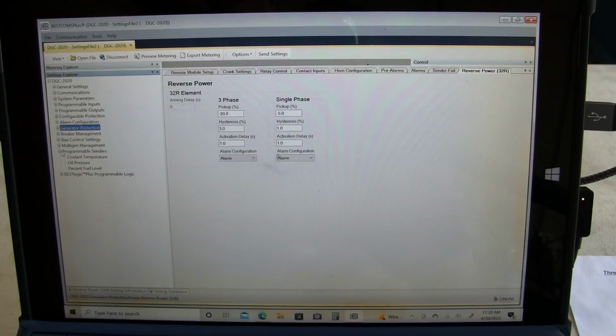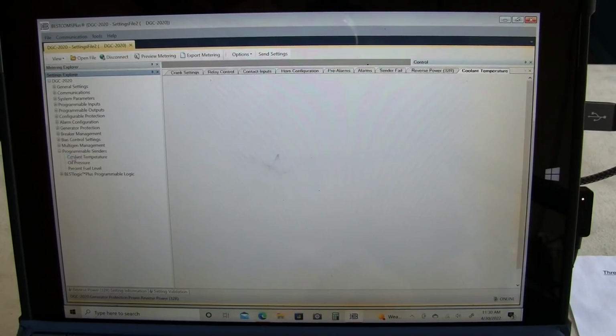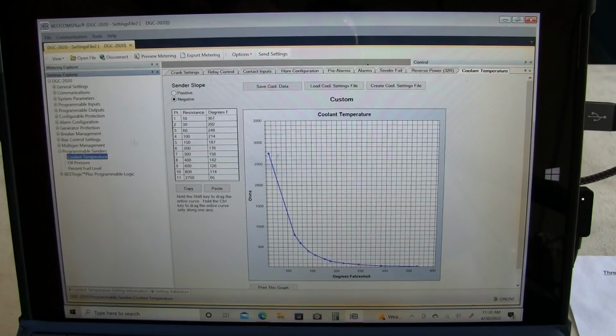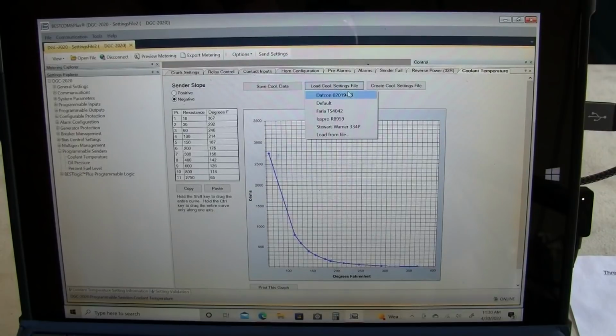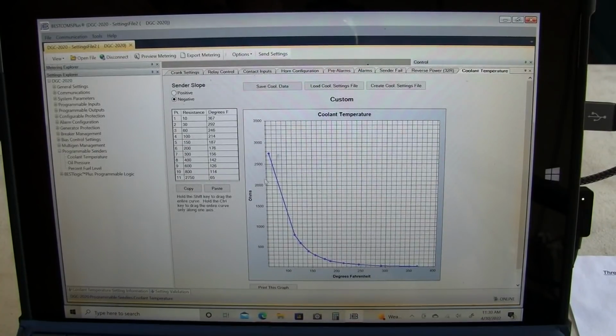Programmable senders. So there are multiple coolant temperature sensors available for these gensets, as well as oil pressure. And let's see. So you can see there's a couple of coolant temp sensors. So you got a DATCON, an ISPRO, Stewart Warner, a couple different pre-programmed ones, but you can also load different resistance curve files. So you can see here's a display of the coolant temperature versus the resistance of the sensor. It's a whole other thing to go into.